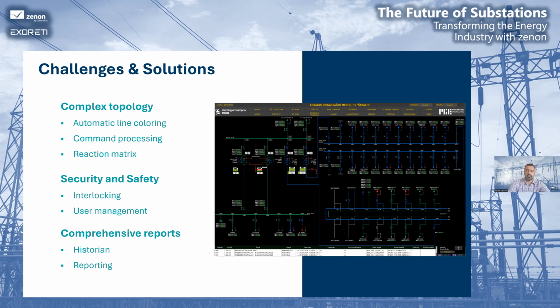To address this complexity, we implemented automatic line coloring to help operators be aware of the voltage presence on the bus. The project was also developed in several stages. We had to prevent maloperation during regular substation operation and keep safety at the highest possible level, so we used command processing, and interlocking was implemented not only at the IED level, but at the SCADA level too.